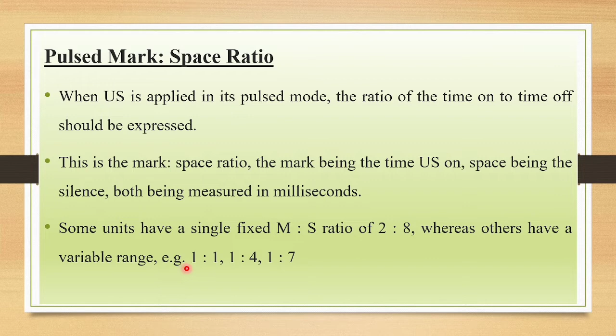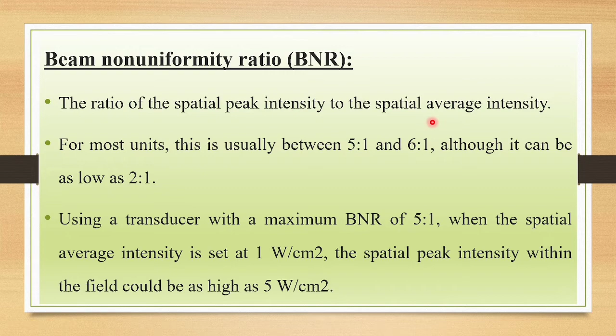The next parameter is the beam non-uniformity ratio. The beam non-uniformity ratio is the ratio of spatial peak intensity to the spatial average intensity. For most units, this is usually between 5:1 and 6:1, although it can be as low as 2:1. Using a transducer with a maximum beam non-uniformity ratio of 5:1, when the spatial average intensity is set at 1 watt per centimeter square, the spatial peak intensity within the field could be as high as 5 watts per centimeter square. So this is the ratio of spatial peak intensity to spatial average intensity.